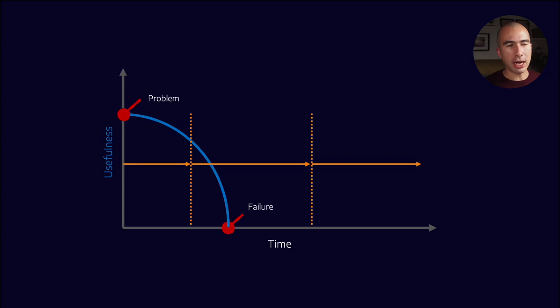Let's say I have this particular instance, a reasonably short P to F interval, so I'm picking a worst-case scenario here, and I have sampled in the latter two-thirds of the P to F curve. How fast does the lab need to turn around the results so that I, as the engineer on site, can identify that there is a problem and take the machine out of service before the catastrophic failure? The reality is, this is the amount of time: the time between me taking the sample and when the machine completely fails. If I can get the lab to turn around the sample result in a shorter amount of time than that, then I should be in the clear.